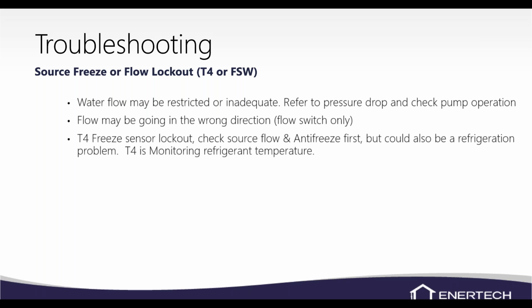A lot of times I see it lock out on the T4 sensor before it locks out on low pressure because the T4 sensor responds faster. So it'll throw you off a little bit when you see that FS lockout, and we tell you, hey, check your refrigerant circuit.